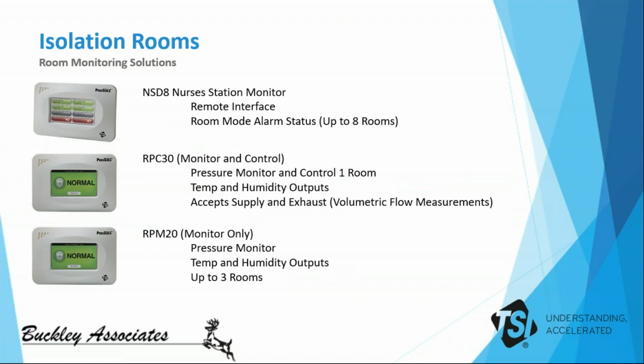So here are some of the most common pressure monitors we're seeing installed on a daily basis. The NSD8 is the nurse's station monitor, and this can be connected up to 8 rooms. It's typically installed so that all nearby rooms can be measured or monitored from one single location, okay? The RPC30 shown in the middle here can both monitor and control one single room. I didn't really touch on it in this presentation. I know we talked about different types of pressure control a little bit, and we usually want to go with volumetric flow, but this device can be used both to monitor and control the pressure in a space.